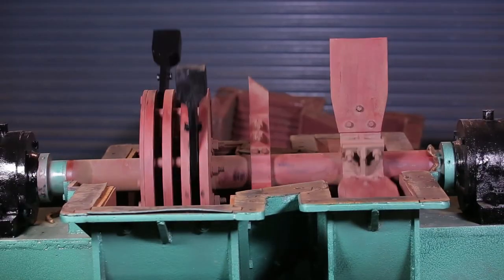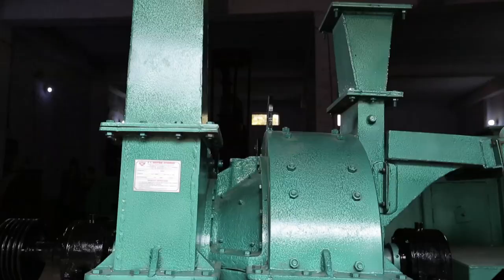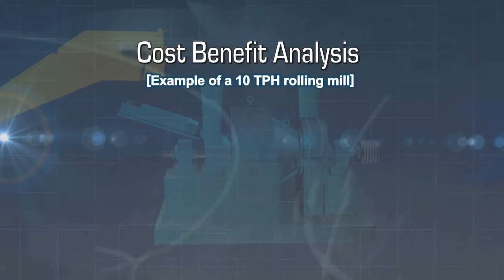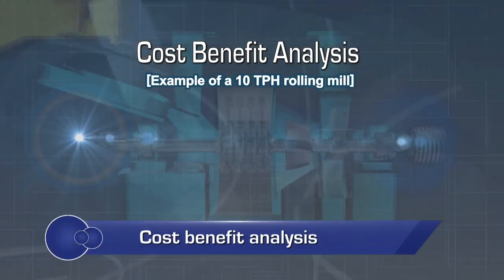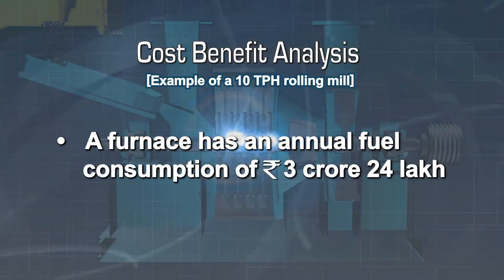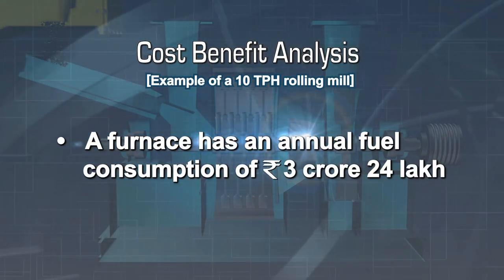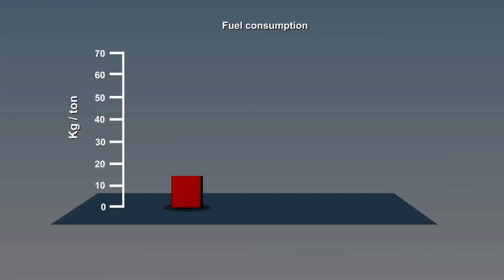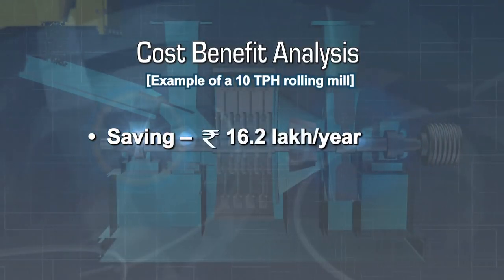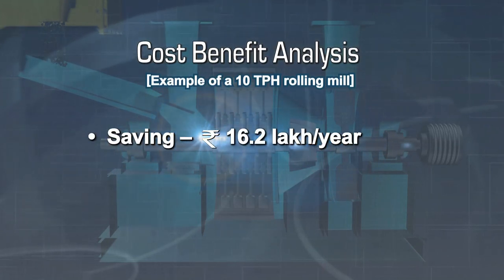The performance of a coal pulverizer can be gauged from the size and uniformity of the coal output. Taking a 10 TPH rolling mill as an example, a furnace will have an annual fuel consumption of 3 crore 24 lakh rupees. With the use of an energy-efficient system, the savings in specific fuel consumption shall be about 5 percent, implying savings of rupees 16.2 lakhs annually.